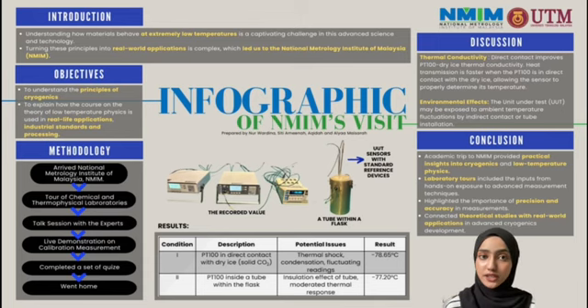The first condition is where PT100 sensors are in direct contact with dry ice, and the result shows negative 78.65 degrees Celsius. This is maybe due to the thermal shock, condensation, and the fluctuating readings. And the second condition is where PT100 sensors are inside a tube within the flask, and the result shows negative 77.20 degrees Celsius. This is maybe due to the insulation effect of the tube and moderated thermal response.